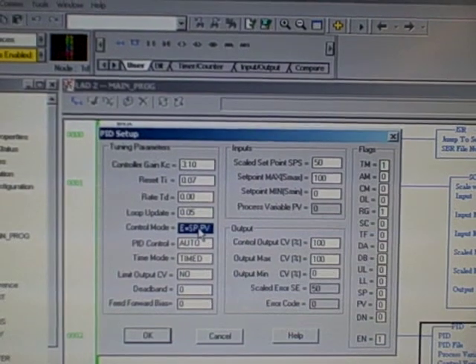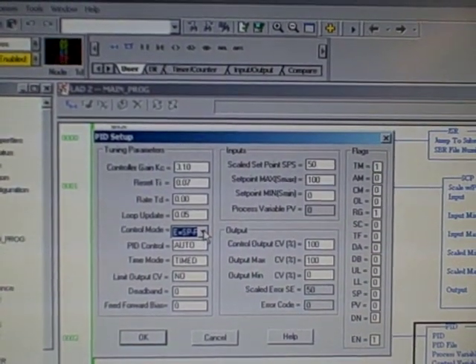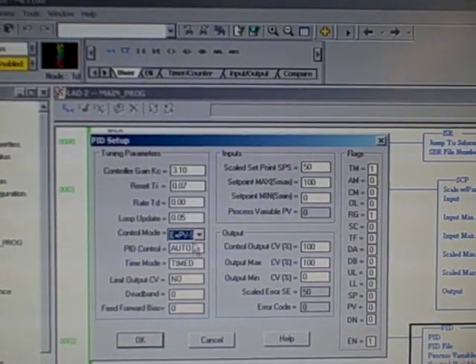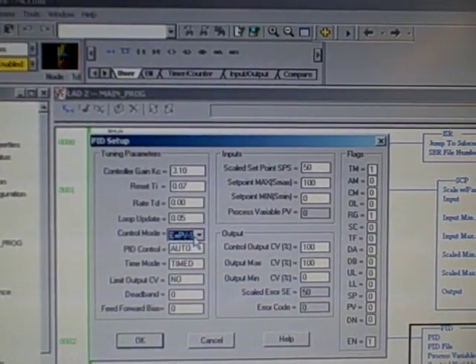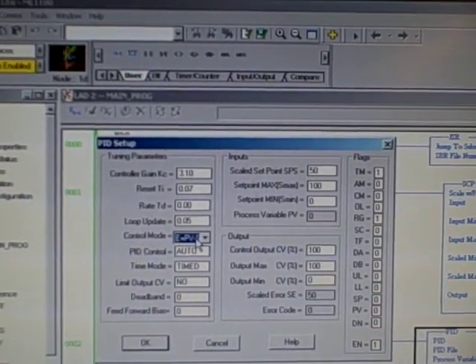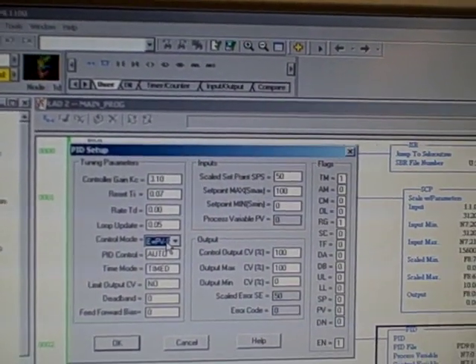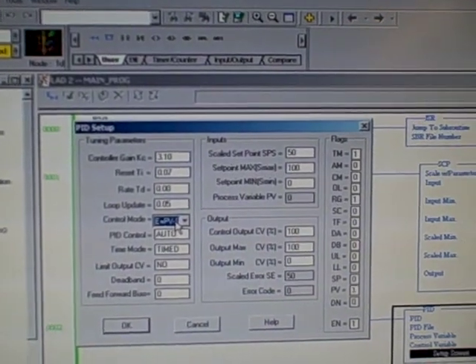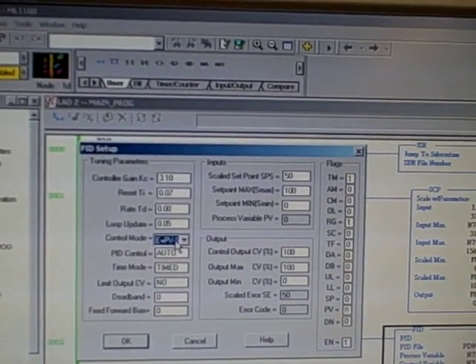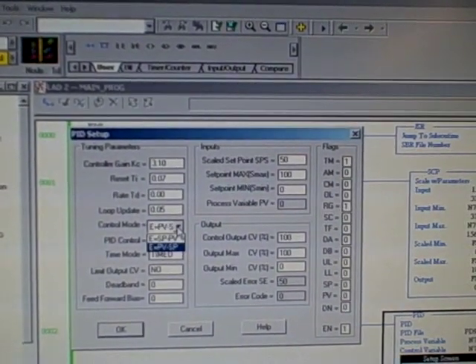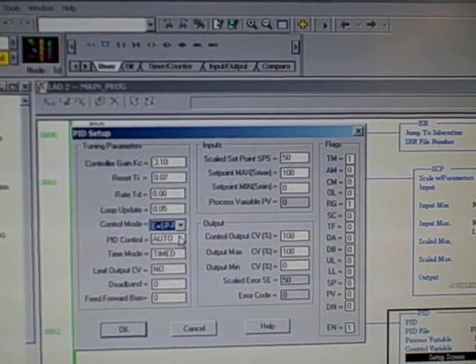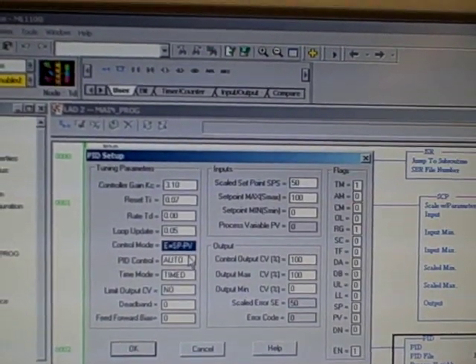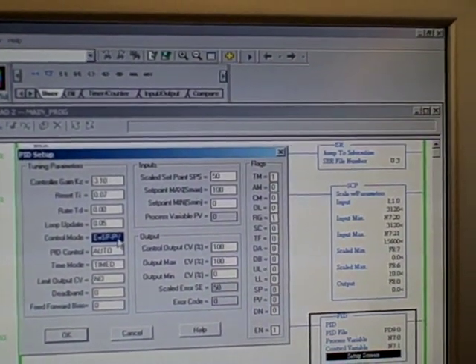If we want to change this to direct action, simply click that, drag down PV minus setpoint. Now that's direct acting. If I were to hit the enter key, this would save that online parameter, and this would be a direct acting controller. I do not have to save the program. I do not have to download to the PLC. I simply make my selection, hit the enter key, and that is it.